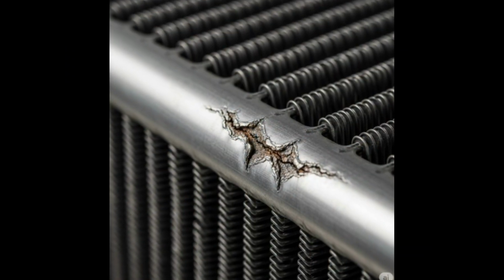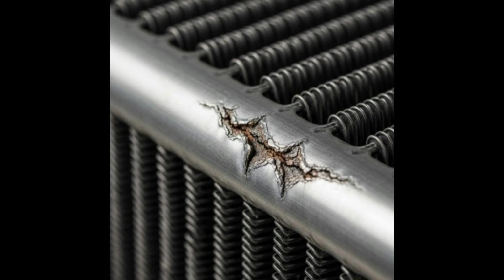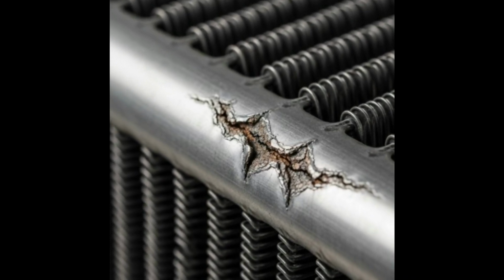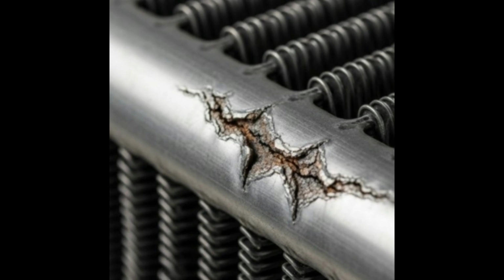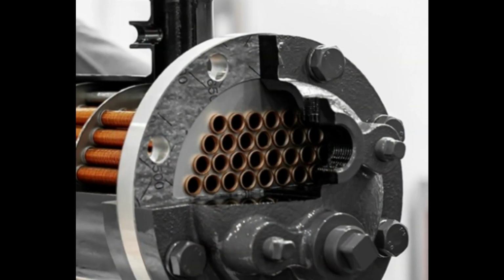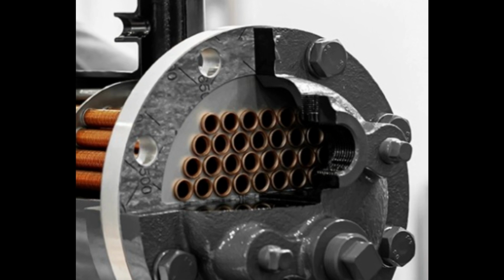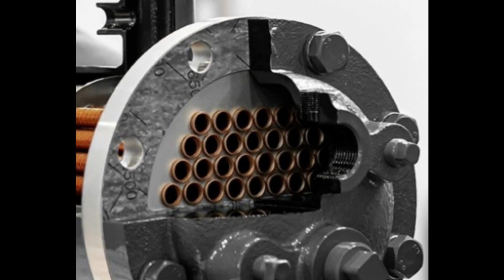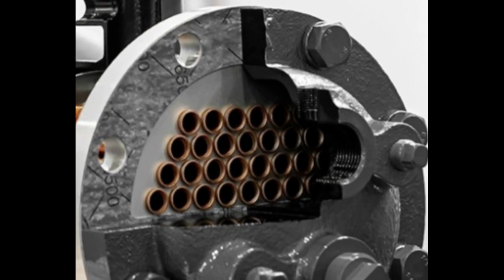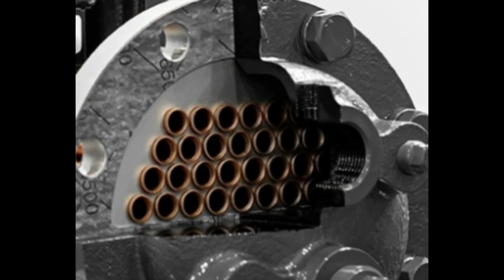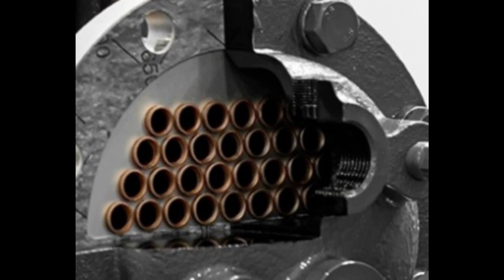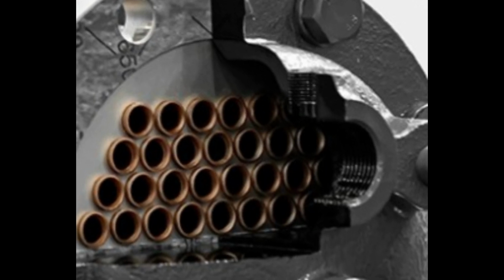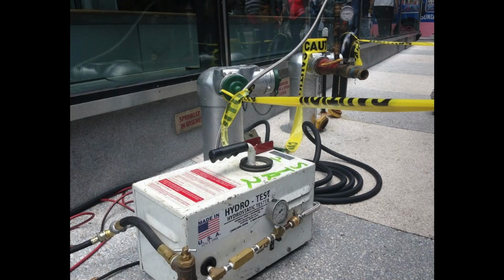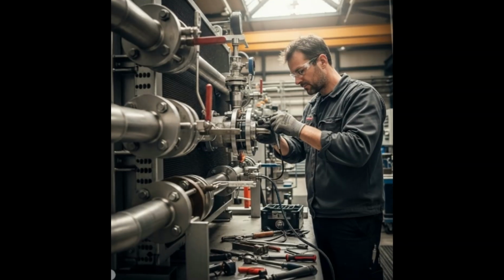Leaks. External leaks are usually found by visible fluid drips, wet spots, or residue on the outside of the exchanger. Internal leaks are usually contamination of one fluid stream by the other. In the case of a cracked heat exchanger in a furnace, the risk of carbon monoxide leaking into a living space occurs. Troubleshooting usually consists of pressure testing, dye testing, and visual inspection.